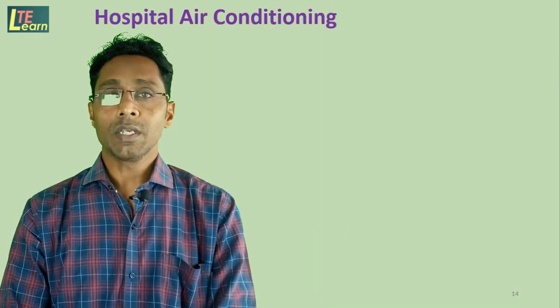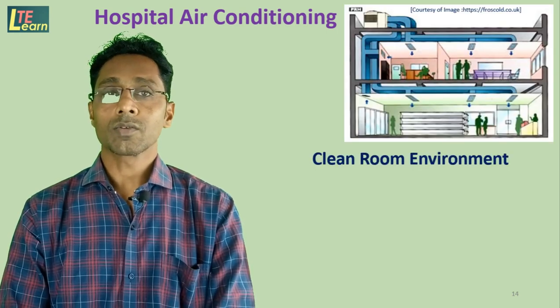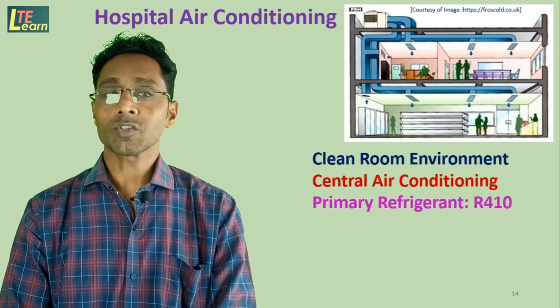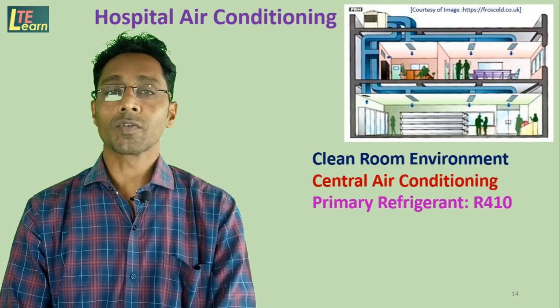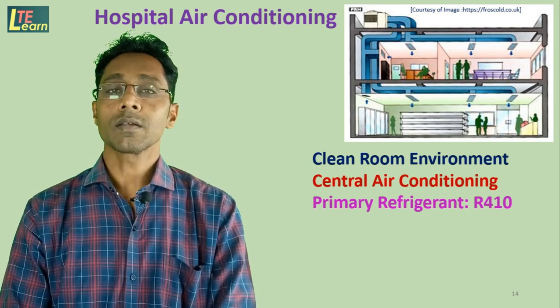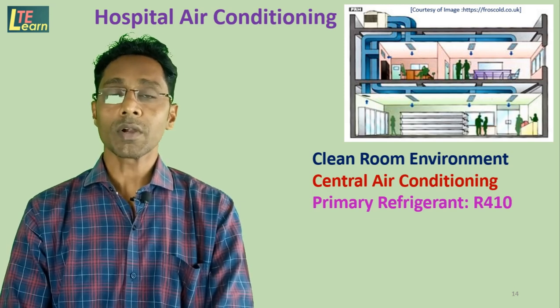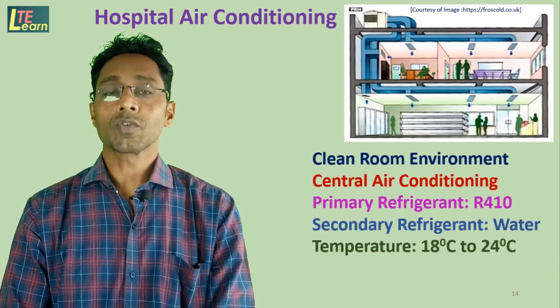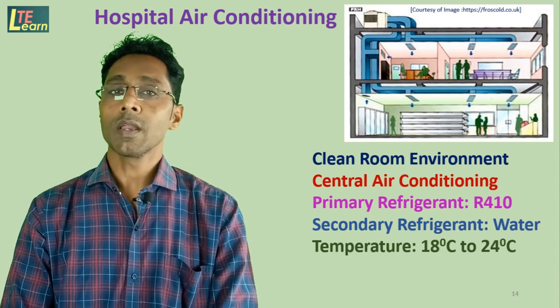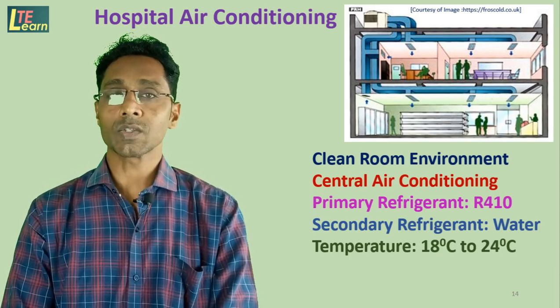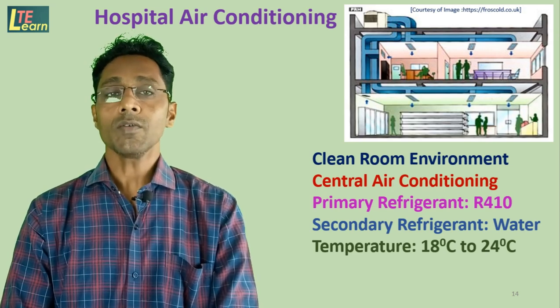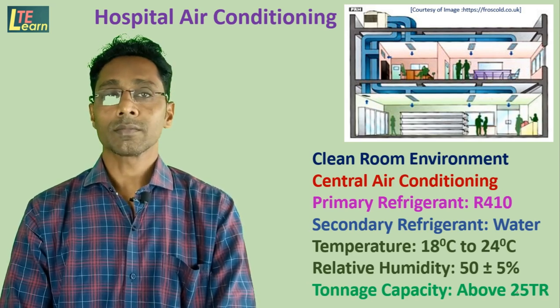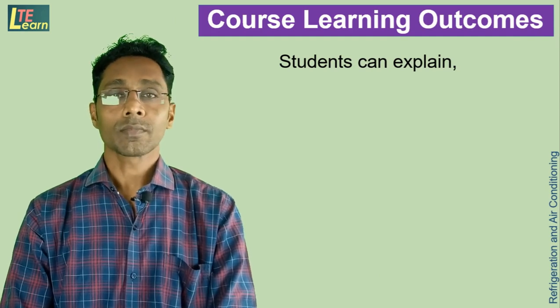Hospital air conditioning: A clean room environment is required, so a lot of care is needed and central air conditioning systems are used. The primary refrigerant is R410A in a VCRS, which cools chilled water at 4 degrees Celsius. This chilled water then cools the air conveyed to various rooms. Room temperature ranges from 18 to 24 degrees Celsius with relative humidity of 55%. Tonnage capacity for hospital air conditioning is above 100 TR.